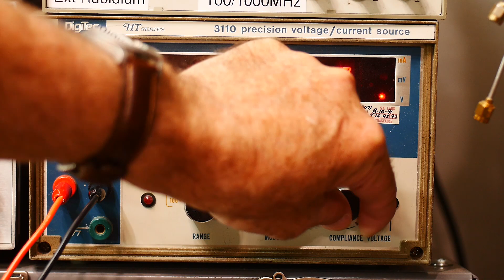So that just says I'm putting voltages on the connector. So you can put it in standby, and then it's disconnected, or normal, and then reverse is just the opposite sign. So now it's -1 volts instead of +1 volts. That's handy for a lot of calibrations where you're doing offsets. It has some nice ranges. It has a 100-volt range, a 10-volt range, and a 1-volt range, and so that's nice.